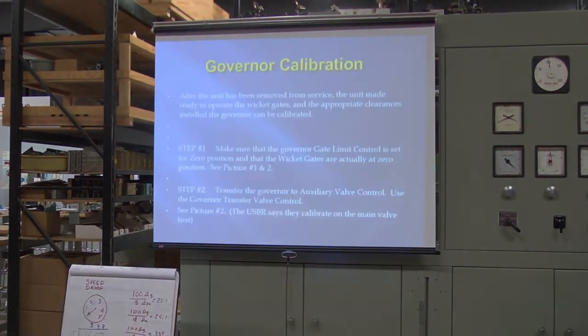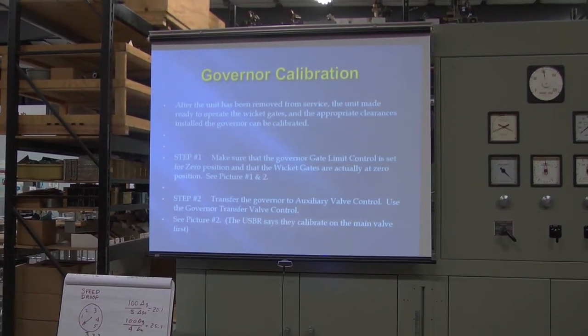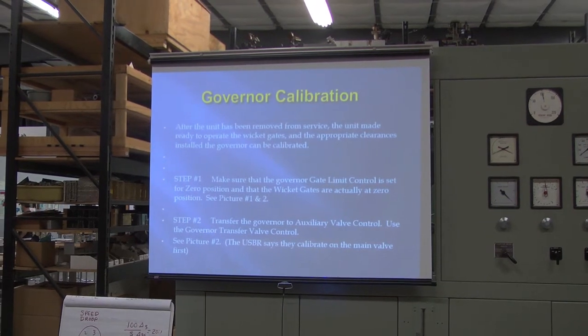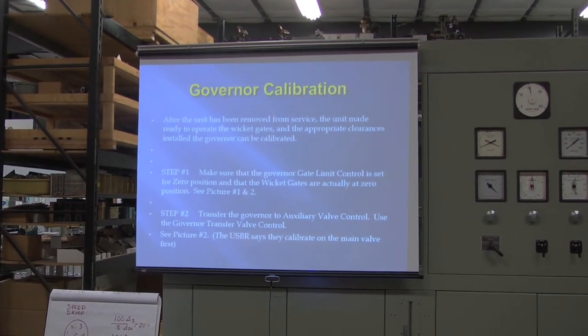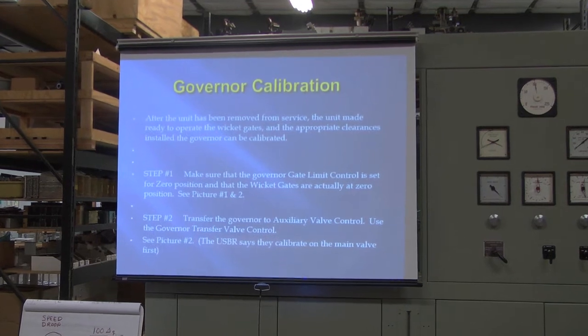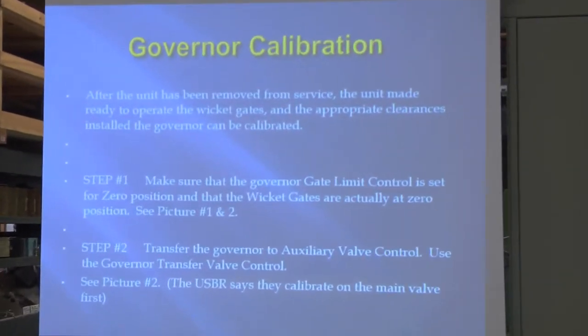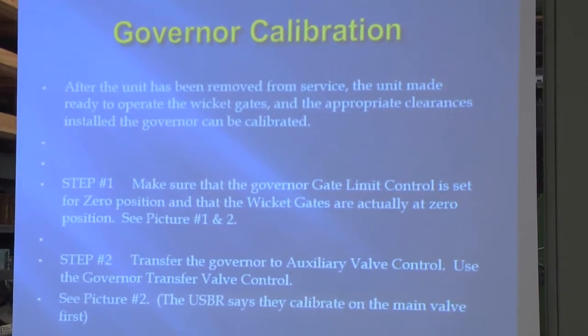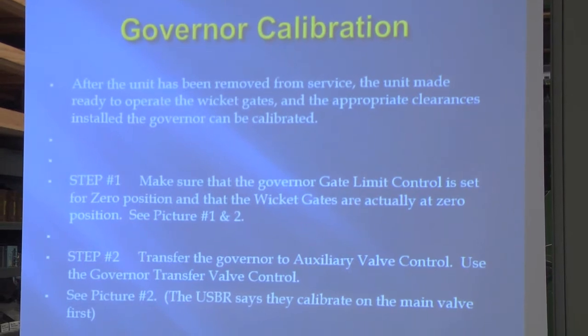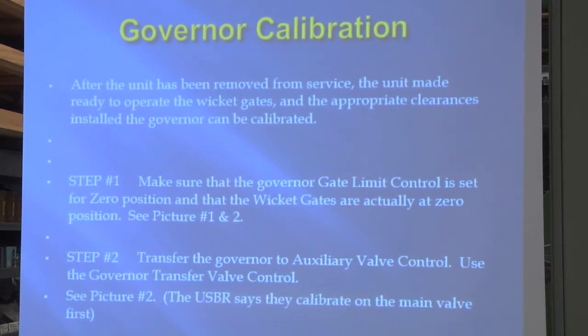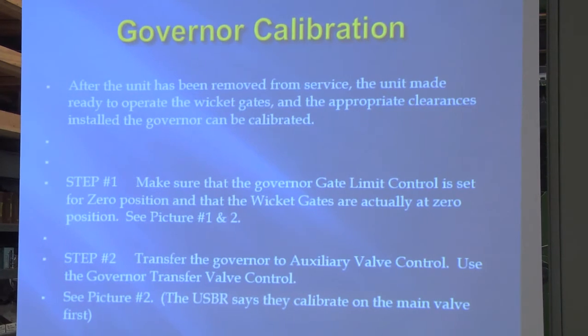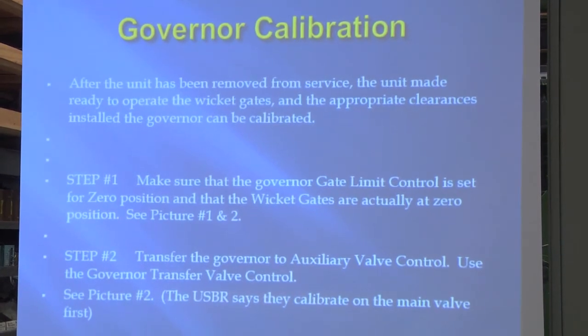Naturally, after the unit has been removed from service, the unit is made ready to operate the wicket gates, and the appropriate clearances installed so the governor can be calibrated. Now this is with the head gate in, okay? It still can be water in the spiral case, depending on your configuration, unless you've got a heck of a lot of tail water, but it won't move anything. That's what we want.